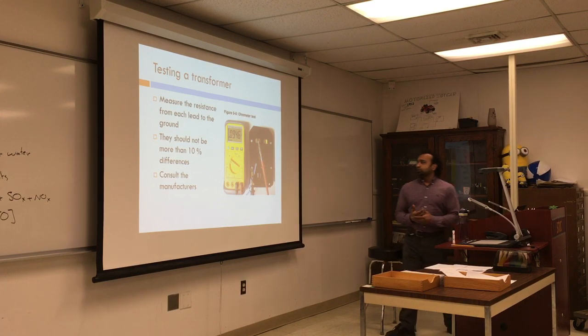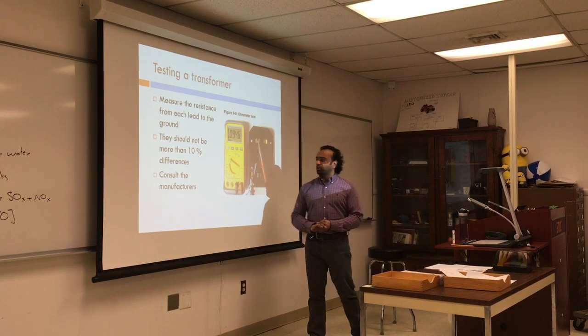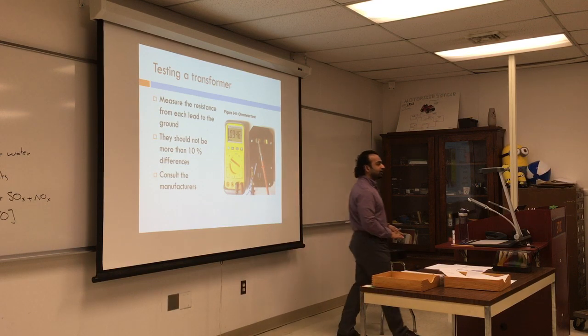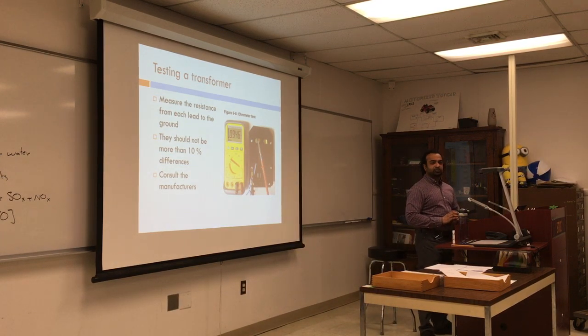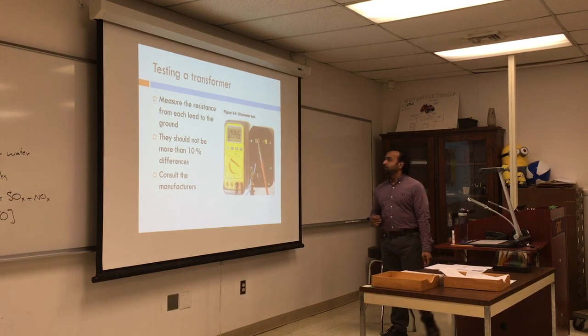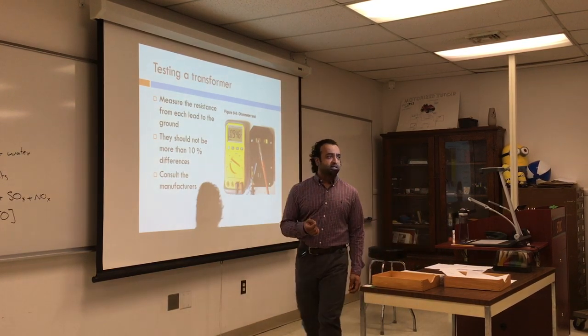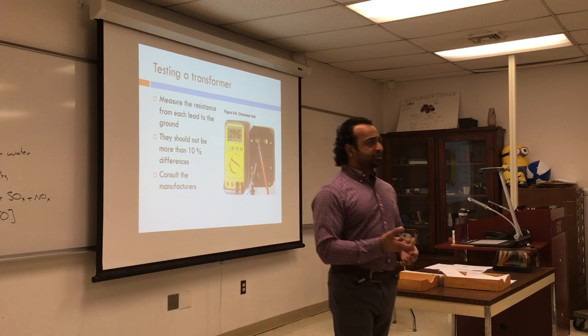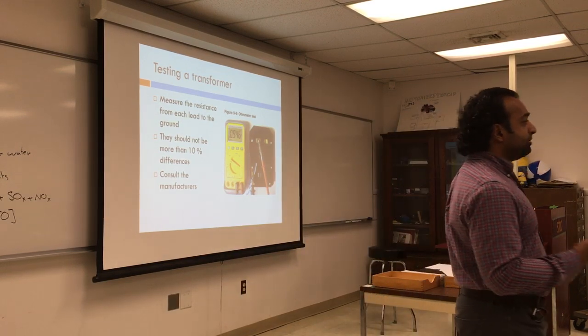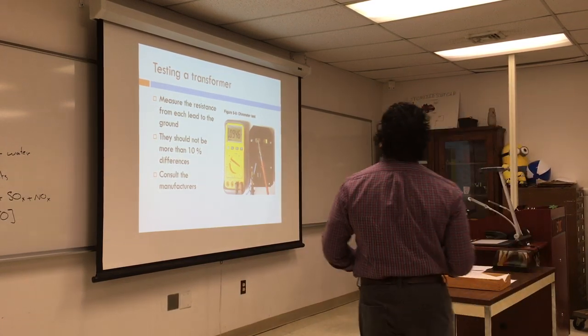When in doubt, you can also consult the manufacturer on how to test those transformers, but usually you can tell if it's giving you enough voltage or not. And one of the best ways to test it is to leave it running and test the amperage, because again, temperature does affect the voltage that comes out of it.